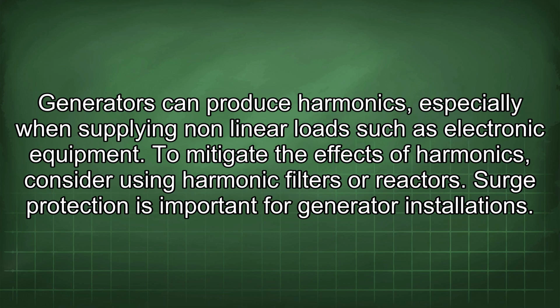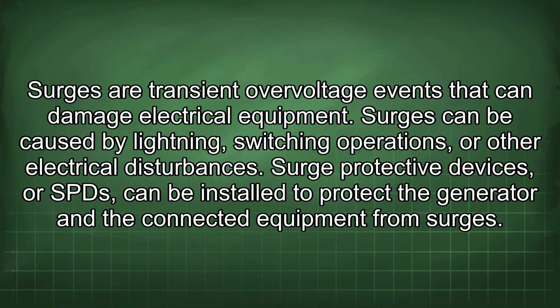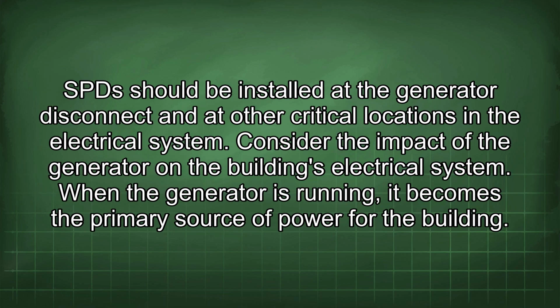Surge protection is important for generator installations. Surges are transient overvoltage events that can damage electrical equipment. Surges can be caused by lightning, switching operations, or other electrical disturbances. Surge protective devices, or SPDs, can be installed to protect the generator and the connected equipment from surges. SPDs should be installed at the generator disconnect and other critical locations in the electrical system.